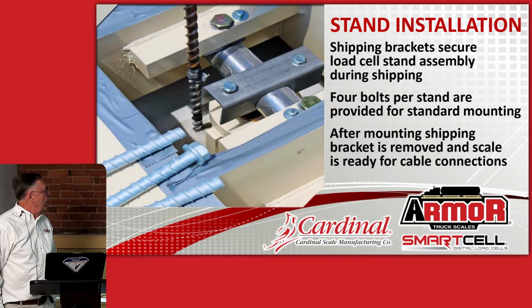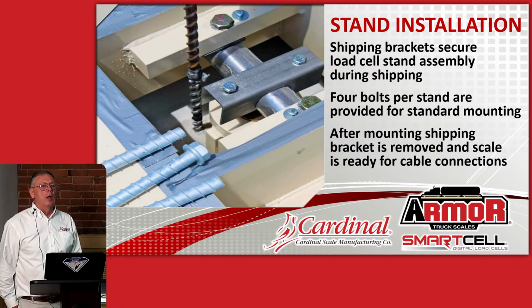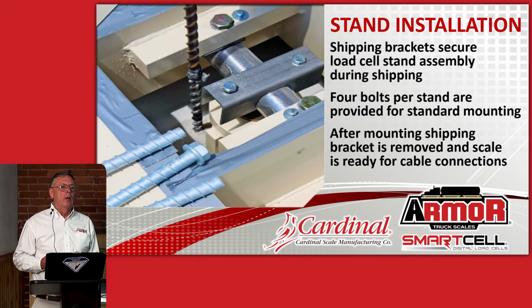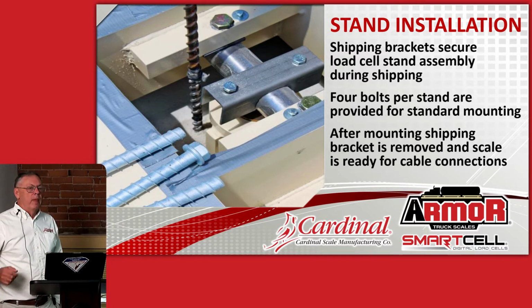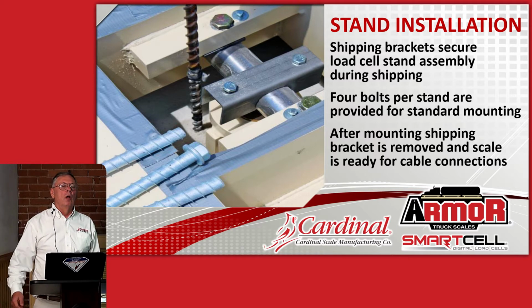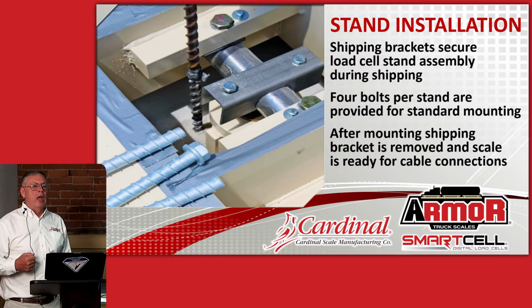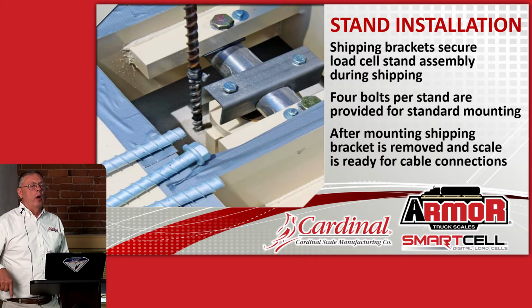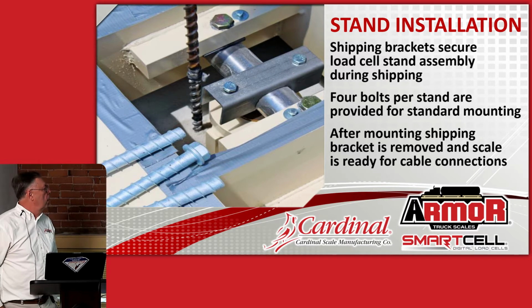Now, those anchor bolts have to be installed with an impact gun, either an air-operated impact or an electric impact. They basically thread into the concrete. So if you try to install them by hand, like with a ratchet, you'll end up just wearing the concrete out. So you have to have a gun so you can really lean on it, put some pressure on it, get it to catch the concrete and thread down in the concrete.